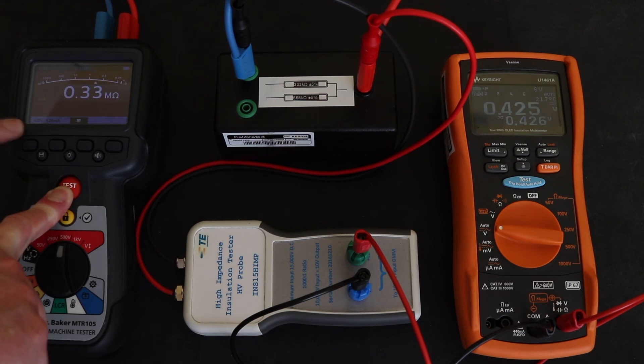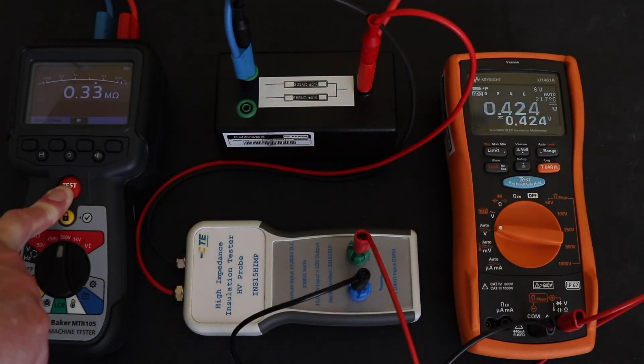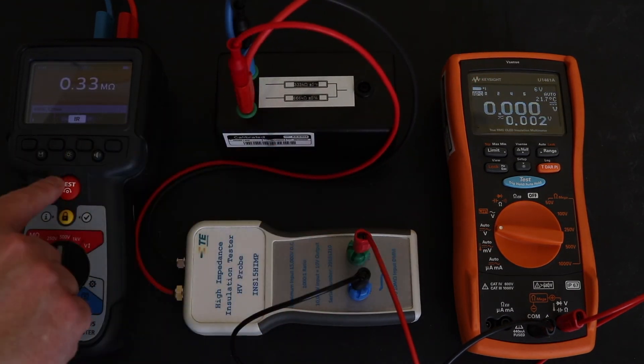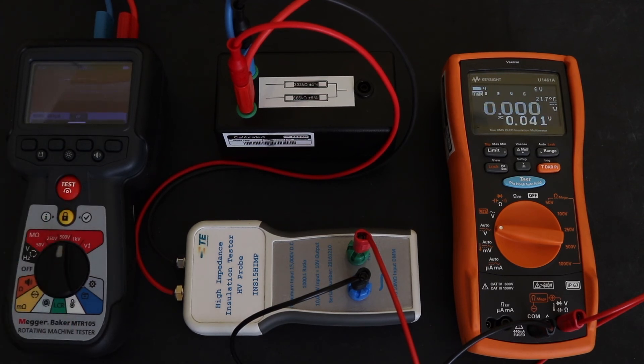And I'm on 421 on here, the instrument's actually showing 424 on the Keysight unit there. And if I sort them over you should see, we'll jump up to 50 now. Yeah, so 505 volts on the instrument, I've actually got 510 shown on the Keysight. So I'd repeat that for a number of resistor values and then I can get a plot of how well the voltage is regulated across this instrument.